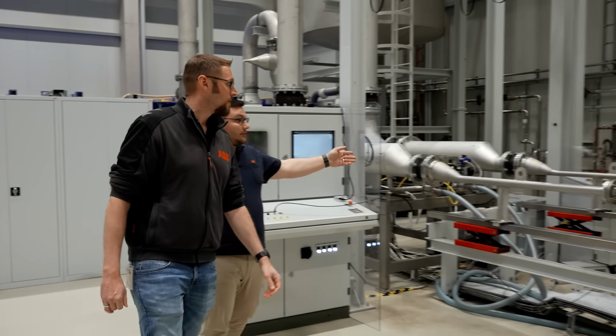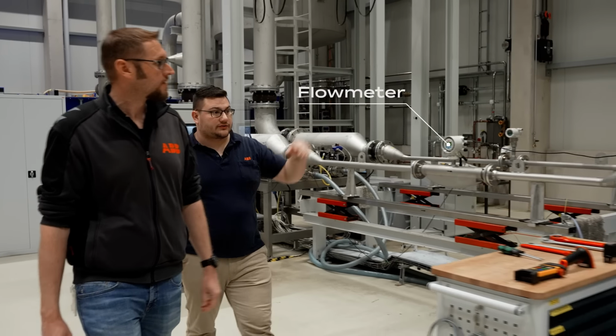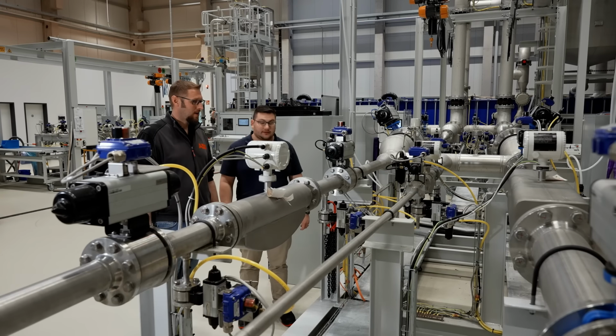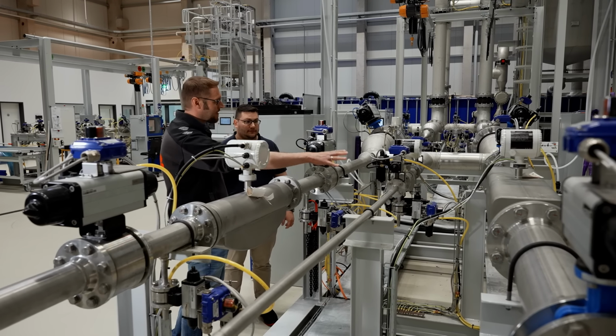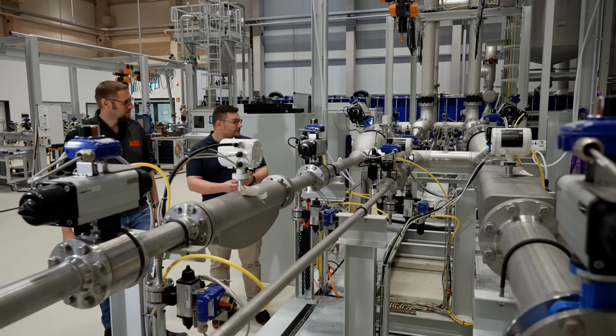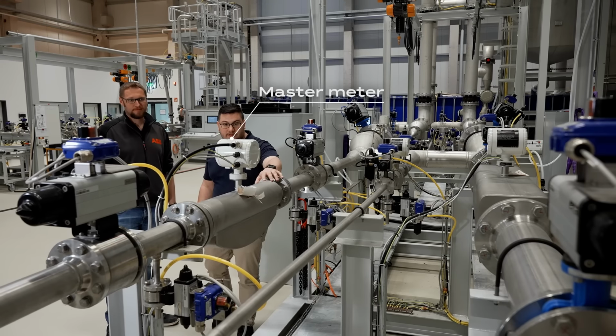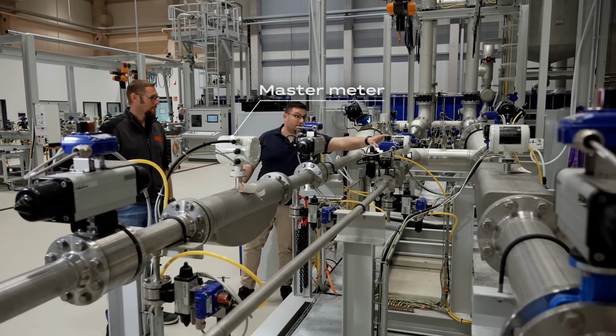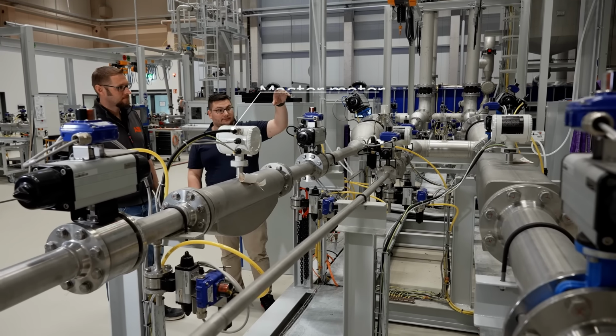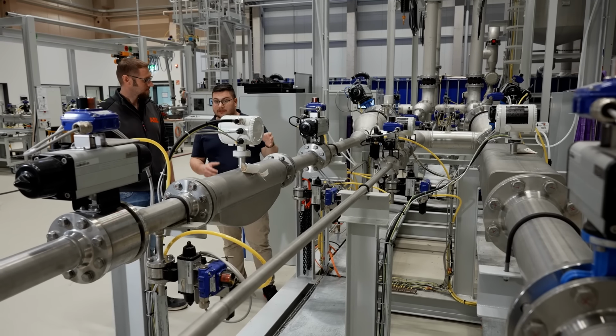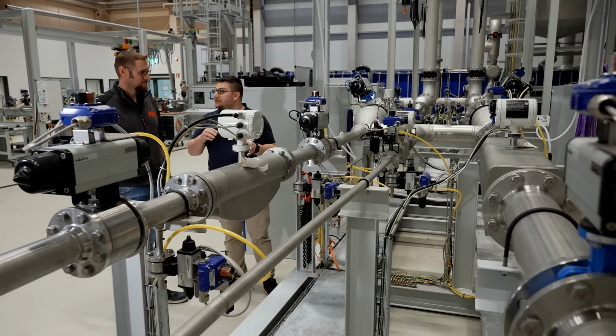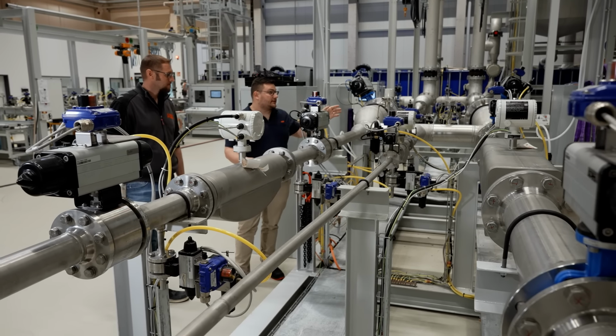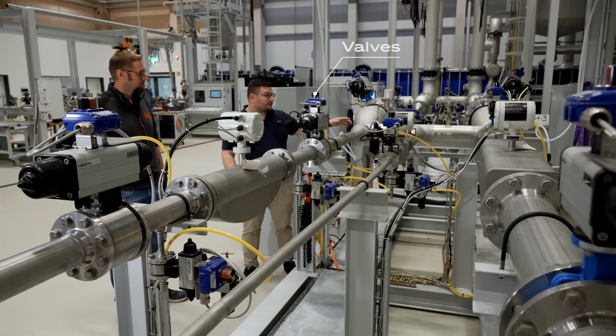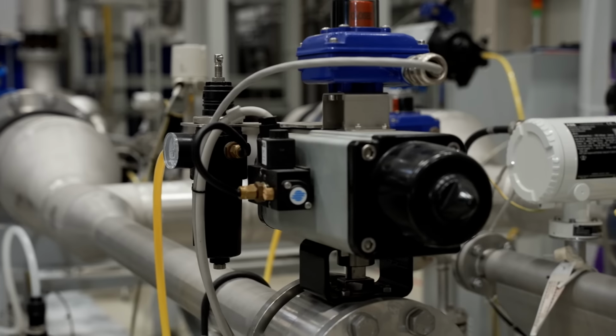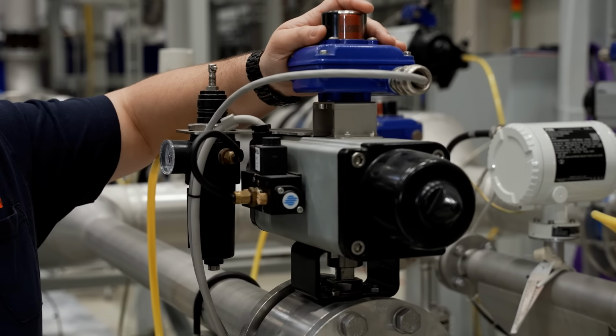We have a test section where the water runs through. Okay. And then it goes to the master meter section. Okay, I see here 3 different lines. Can you explain to me why? Of course. So we have 3 different master meters, of different sizes, this one, the smaller one, and the bigger one. With those, we can actually assure the quality of the flow points, and we have the accuracy depending on the flow rate in the test meter. With the valves, we can actually direct the flow through the different master meters. So the water comes from the test meter, goes through this valve, into this master meter, and back to the tank.